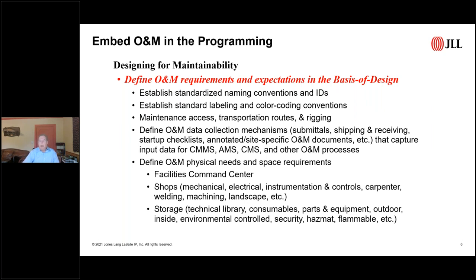You need to then carry that process forward into the basis of design, which is typically performed by the engineer of record and the architects. So at this point, when they're designing how big the pipes are, how long the wires will be, how large a cooling tower needs to be, and all the other physical attributes of the building, you also need to start defining things like naming conventions and identifications for different pieces of equipment or rooms, etc. You need to look at standard labeling and color conventions.